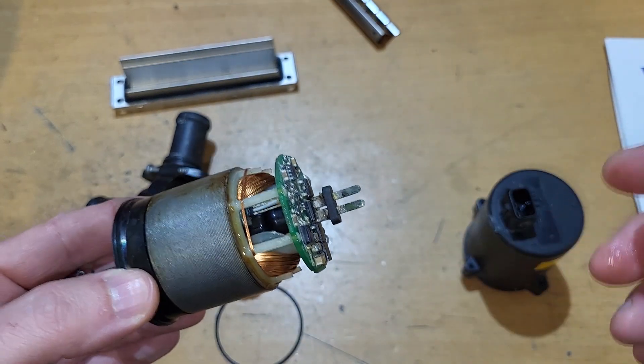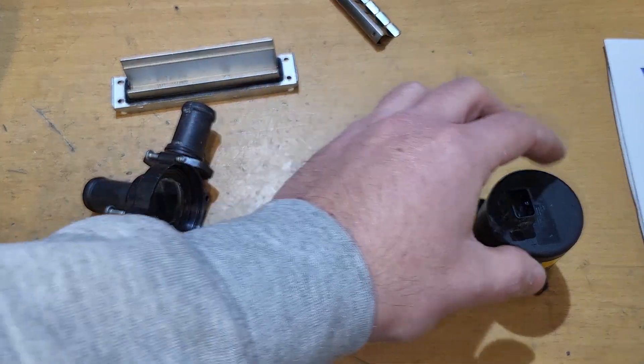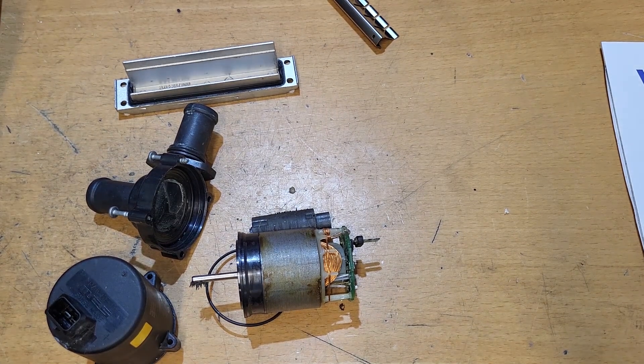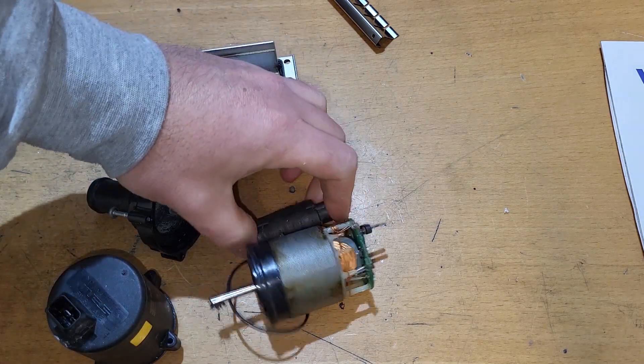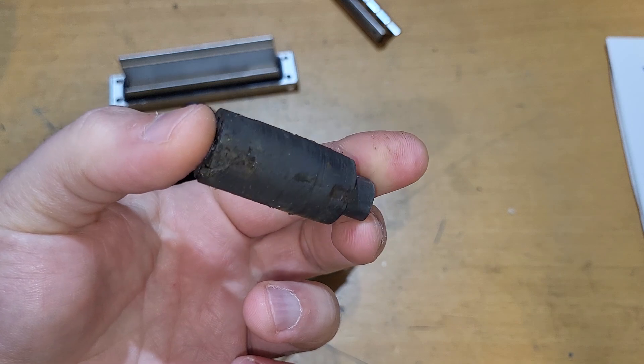This is part one — they damaged the pump. We'll give them another pump, but of course not for free, because this cannot be a warranty claim if they opened the pump. We can also see debris on the magnet, which is clearly not a warranty situation — the circuit needs to be clean.